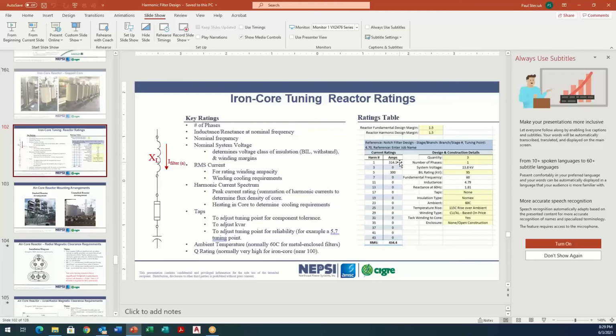But that's not always conservative, because I might have a system where I have 300 amps of fifth harmonic current. If that was the case, I would say it's not a conservative design. I would say you should go to something at least 1.5 times that, if not more. So we design the harmonic currents and the tuning points in a way that, and I'll give you an example, I think is the best way to do it. If I were to do an analysis and I determined that my fifth harmonic current flowing into the filter is, say, 50 amps, I would at that point say that the fundamental current of that filter branch should be 100. I would double it.